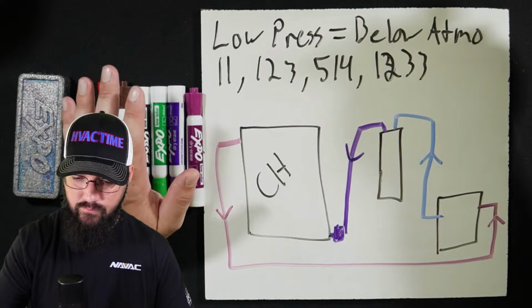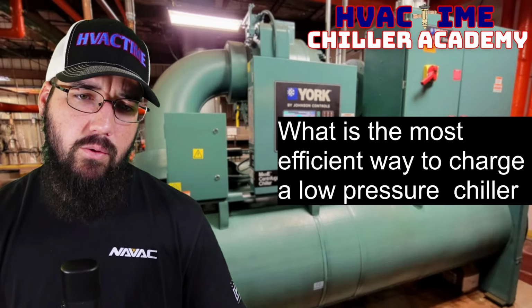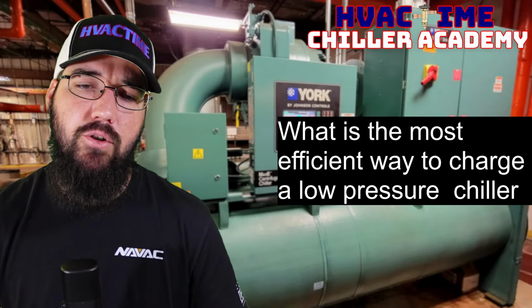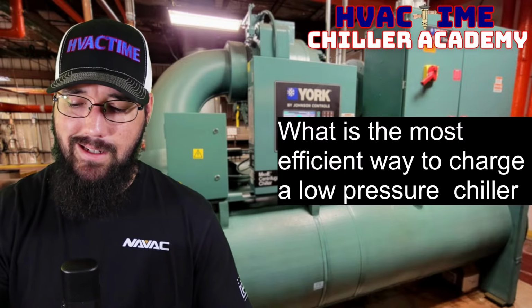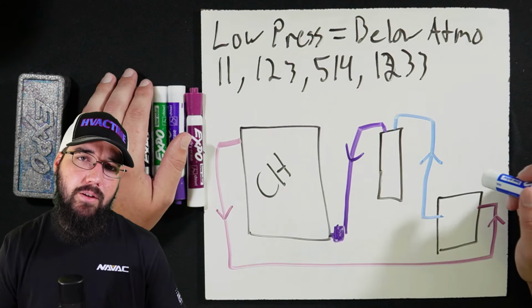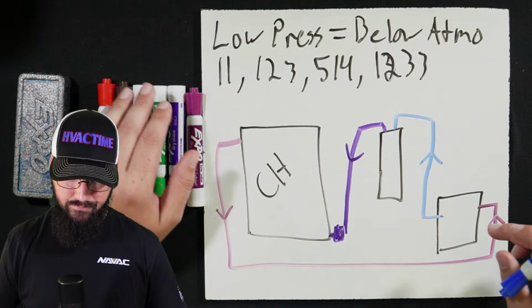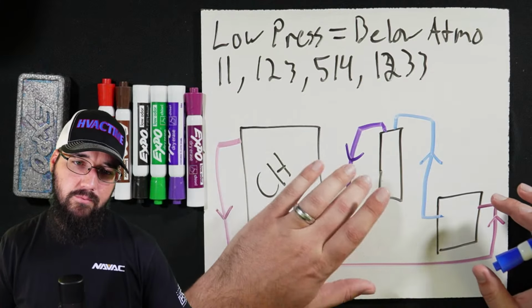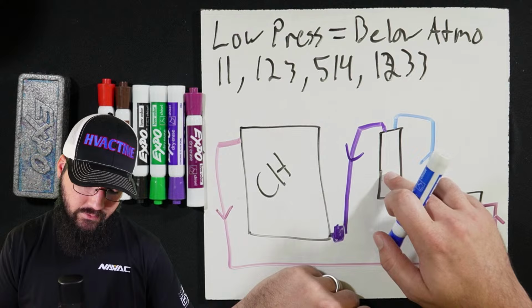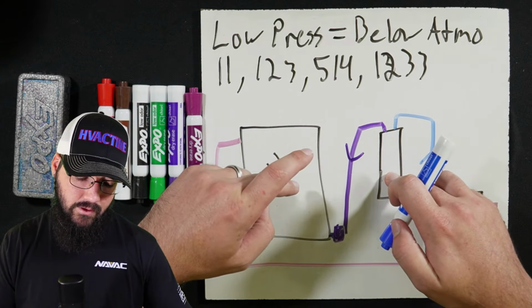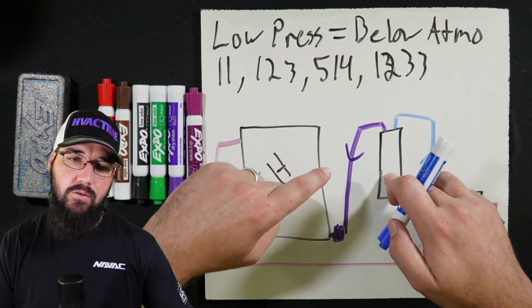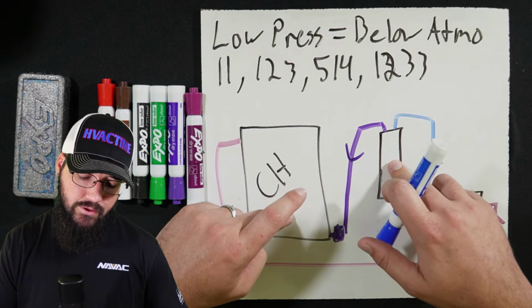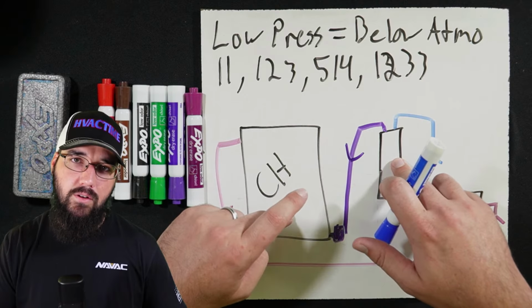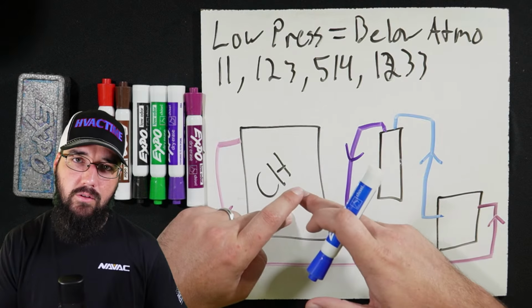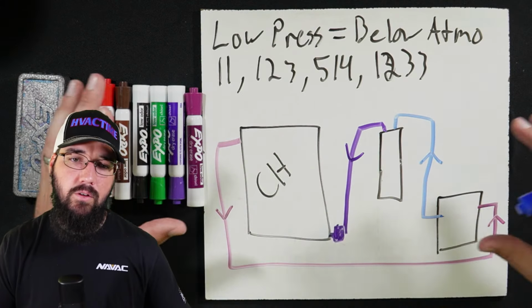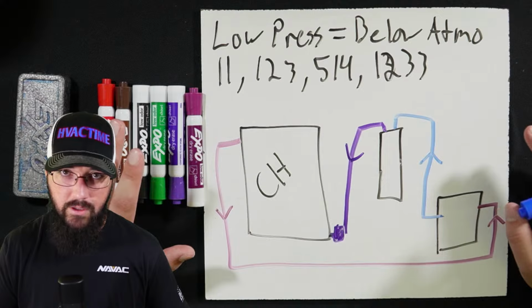Anyway, back to the core premise of our question. What is the most efficient way to charge a low pressure chiller? That is going to be the push-pull method here. Pulling vapor, pushing that vapor into our recovery cylinder. The lower pressure in the chiller draws the liquid in. The higher pressure in the cylinder pushes liquid in. They both work in unison, and it moves a lot of refrigerant really fast.